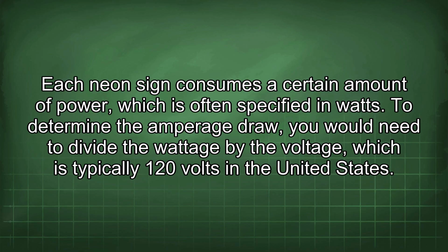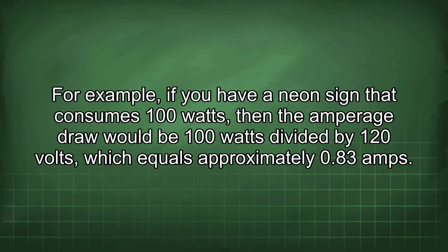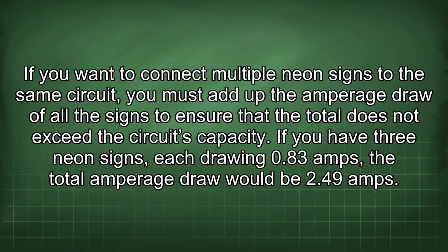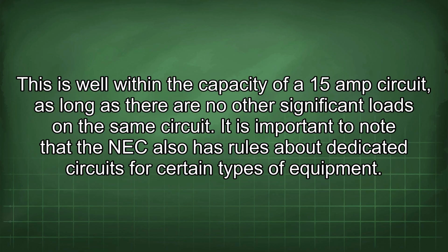Each neon sign consumes a certain amount of power, which is often specified in watts. To determine the amperage draw, you would need to divide the wattage by the voltage, which is typically 120 volts in the United States. For example, if you have a neon sign that consumes 100 watts, then the amperage draw would be 100 watts divided by 120 volts, which equals approximately 0.83 amps. If you want to connect multiple neon signs to the same circuit, you must add up the amperage draw of all the signs to ensure that the total does not exceed the circuit's capacity. If you have 3 neon signs, each drawing 0.83 amps, the total amperage draw would be 2.49 amps.